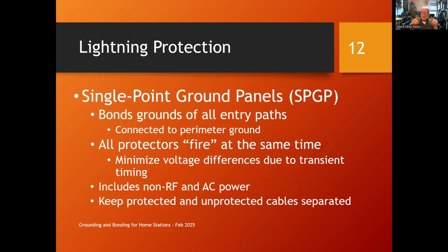And everything that comes in from the outside goes through a protector of some sort, and that protector is grounded to the panel. So all of your protectors that are mounted on that panel, when the lightning surge comes, they all fire at the same time. And I was not sensitive to this until Ron Block explained it to me. I said, wait a minute, you want them to fire at the same time. It's not enough to just have protectors all over the place. You want them to fire at the same time.